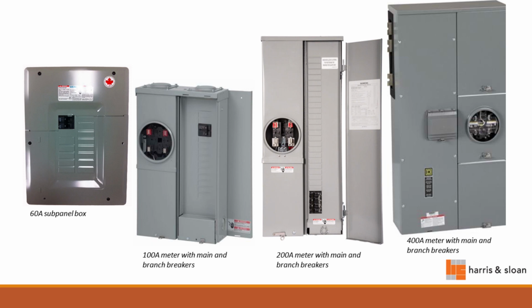One thing we've noticed doing projects that need more than 200 amps is that this is a new emergent space. We've had to look at the technology that's available, and it's still emerging. Some meter boxes being designed by manufacturers are coming in Q3 that are more code compliant. But at the moment, a lot of what we've had to do is take our designs to our supplying utility to make sure they're happy with what we're putting together, because the market is really trying to catch up to this need for a larger breaker box in some of our projects.